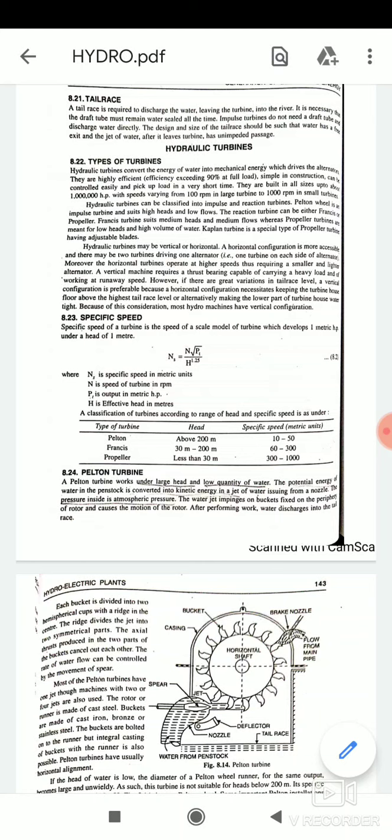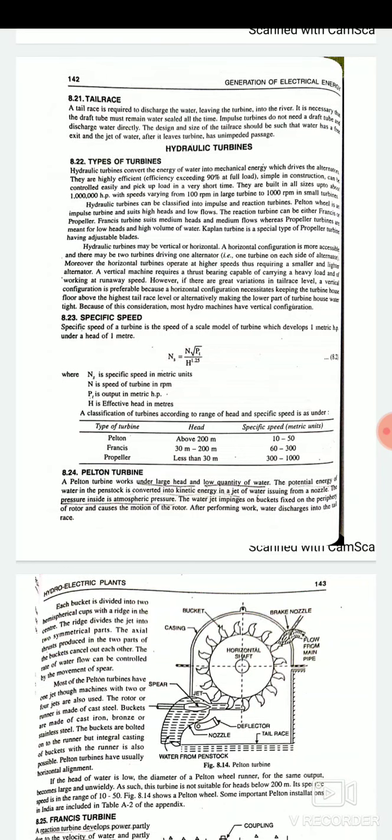Hydraulic turbines can be classified into impulse and reaction turbines. Pelton wheel is an impulse turbine and suits high heads and low flows. The reaction turbine can be either Francis or propeller. Francis turbines suit medium head and medium flows whereas the propeller turbines are meant for the low heads and high volume of the water. Kaplan turbine is a special type of propeller turbine having adjustable blades.